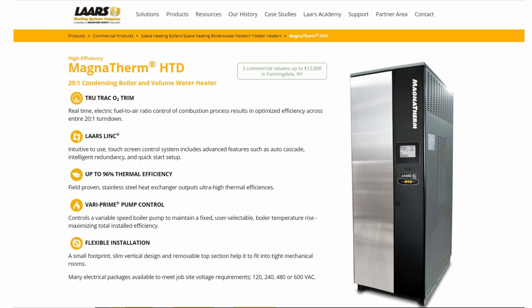So we have so many new products, I can't spend too much time on that. So we have the Magnatherm high turn down, or 20-to-1 condensing boiler and volume water heater. So everybody's been screaming, we want higher turn down, higher turn down. We weren't ready to do it until we figured out how to do it well. And the top line thing here is the Tru Trac O2 trim, which is the reason why we were able to do it really well. It's a real-time electronic fuel air ratio control. It controls the full combustion process to give you optimized efficiency throughout the whole turn down. So if we're turning down at 17% or 17-to-1, it's going to measure everything and recalibrate and give you the highest efficiency and best flame.